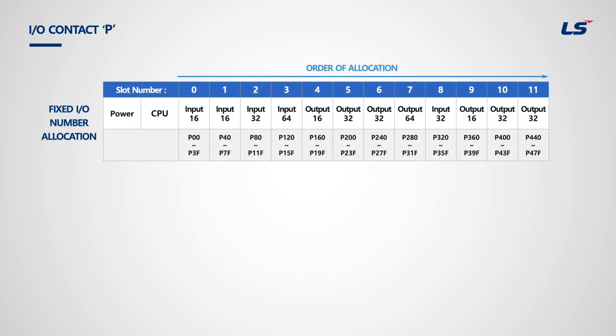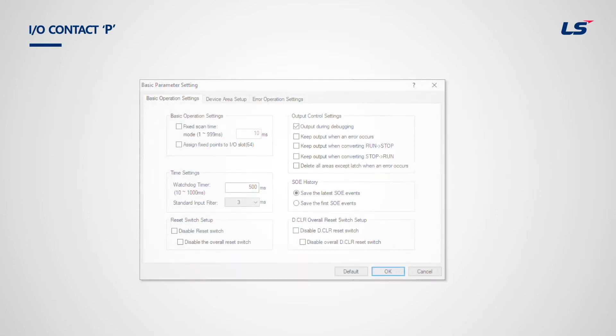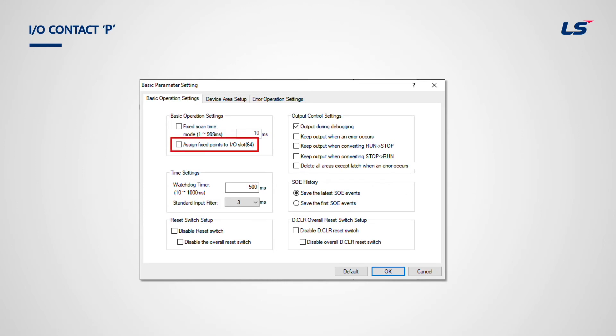The allocation of input-output numbers gives an address to the input-output terminal of each module in order to read data from the input module and print data to the output module during operation. XGK provides two kinds of input-output allocation: fixed and variable. By selecting 'Assign fixed points to input-output slot' from basic parameters, 64 points are allocated to each slot regardless of module. Users do not need to change programs even if they change the module later.